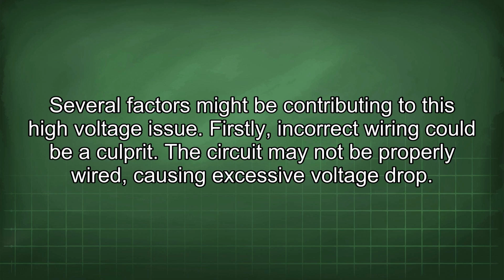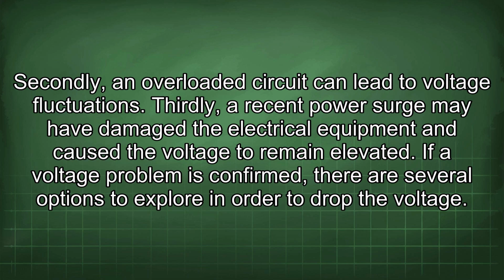Firstly, incorrect wiring could be a culprit. The circuit may not be properly wired, causing excessive voltage drop. Secondly, an overloaded circuit can lead to voltage fluctuations. Thirdly, a recent power surge may have damaged the electrical equipment and caused the voltage to remain elevated.